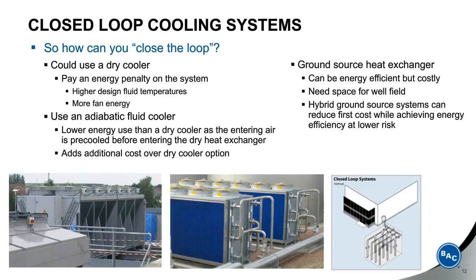On a typical chiller system, water-cooled chiller, you're operating around 0.6 kW per ton. The heat rejection operates at 0.06 kW per ton, or 90% less. So you want to protect and have the energy reduction on the higher energy part of the system, which would be, in that case, the chiller. It also requires more fan energy to do the cooling in a dry mode. You have to move a lot of air there compared to the evaporative cooling process.